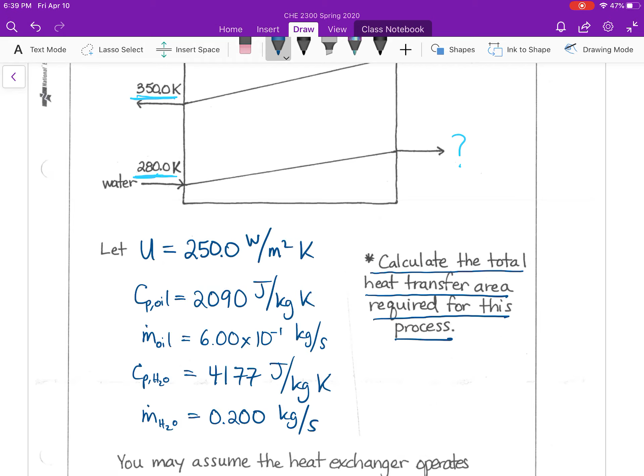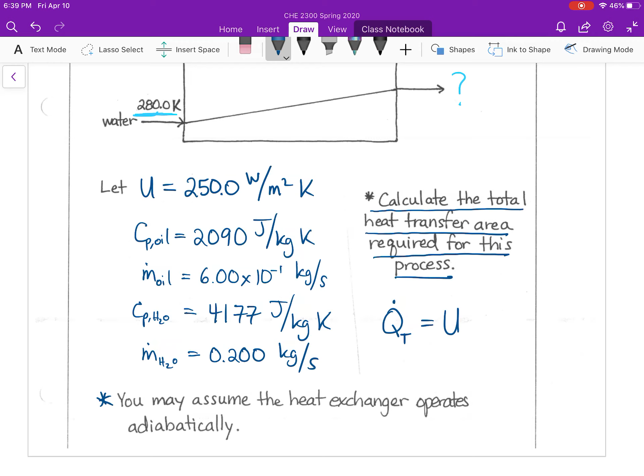So I can go to my overall design equation, which tells me that the total heat flow is equal to the overall heat transfer coefficient multiplied by the total area of heat transfer, multiplied by the log mean temperature difference.